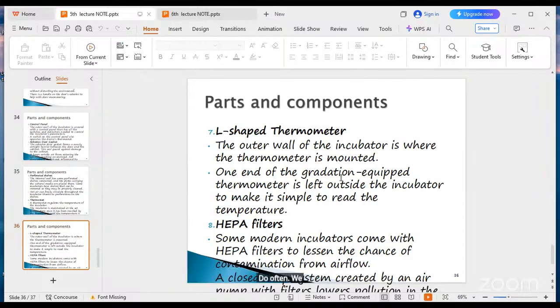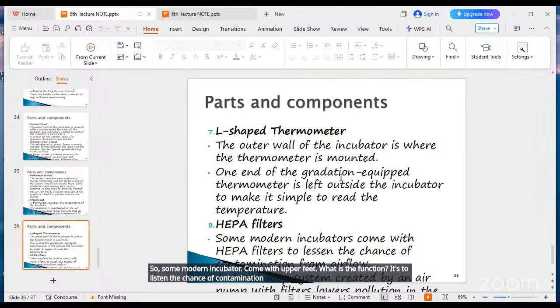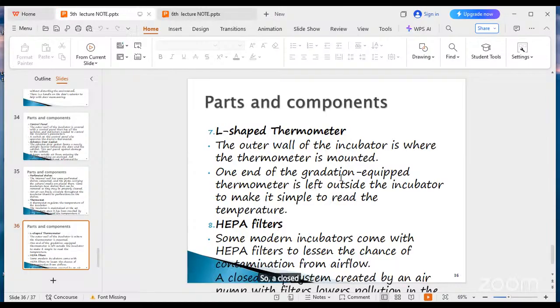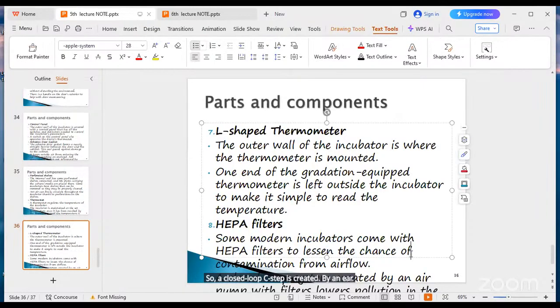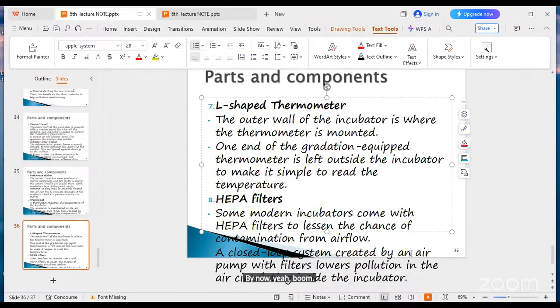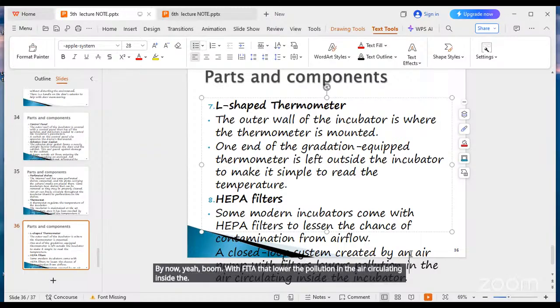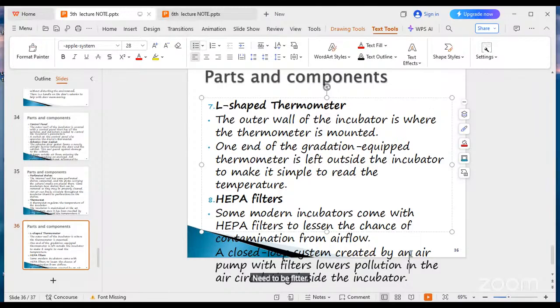We have the HEPA filter, high efficiency particulate air filter. Some modern incubators come with a HEPA filter. What is the function? It is to lessen the chance of contamination from air flow. So a closed loop system is created by an air pump with a filter that lowers the pollution in the air circulating inside the incubator. Air that circulates inside the incubator needs to be filtered, and it is the function of the HEPA filter to do that.